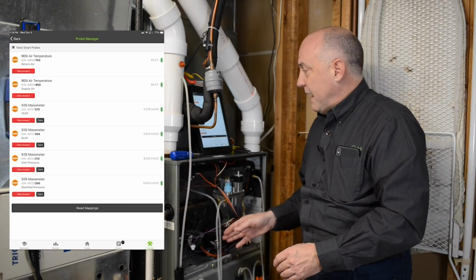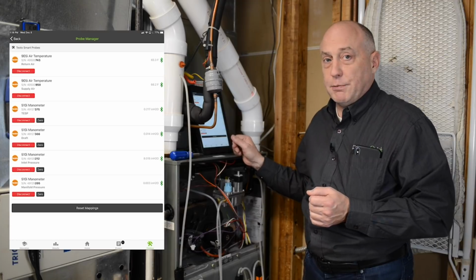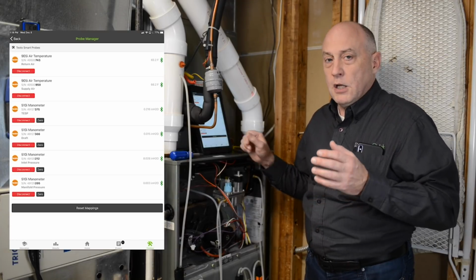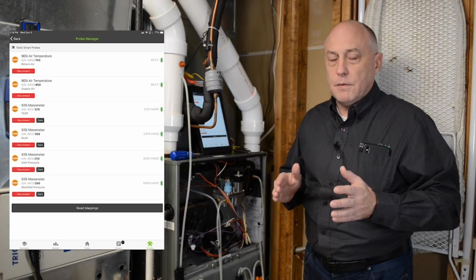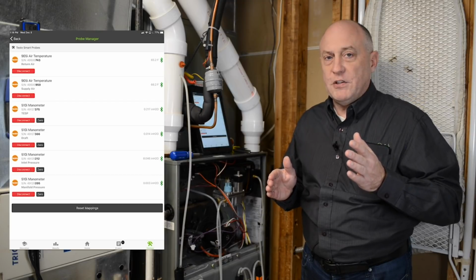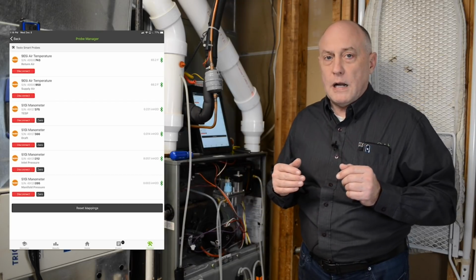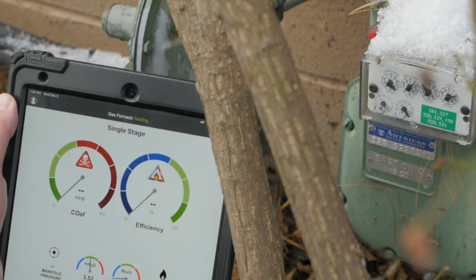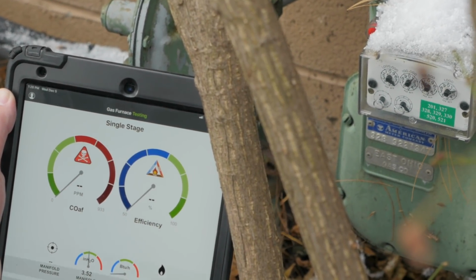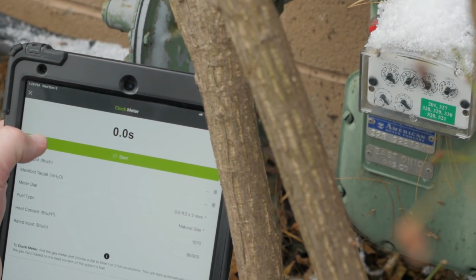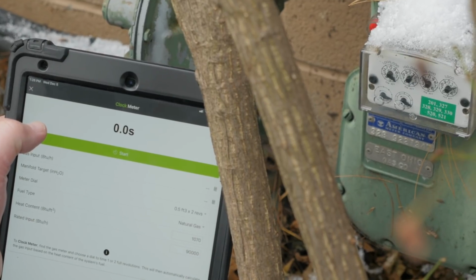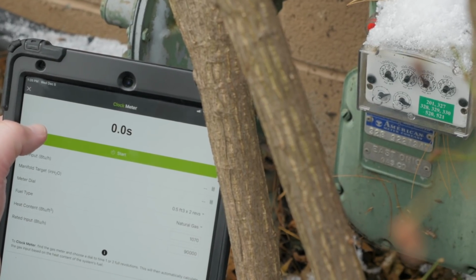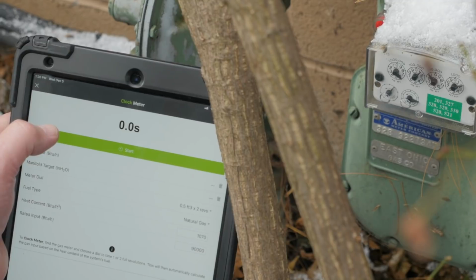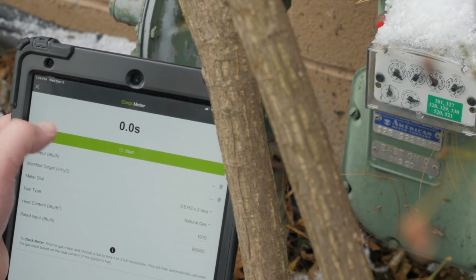So now when I open this back up to the gas, you'll see my incoming gas pressure is about 8 inches of water column. So I'm going to go ahead and turn this furnace up. We'll get this set to 3.5 inches of water column, and then we'll go out and clock the meter and get started. All right, so I'm going to clock the meter. I'll hit clock the meter here, and we'll wait for the meter to get to the top of the dial, and we'll push start. So we're just about there now, and start.